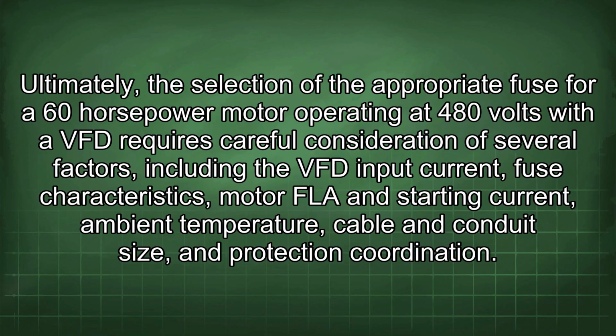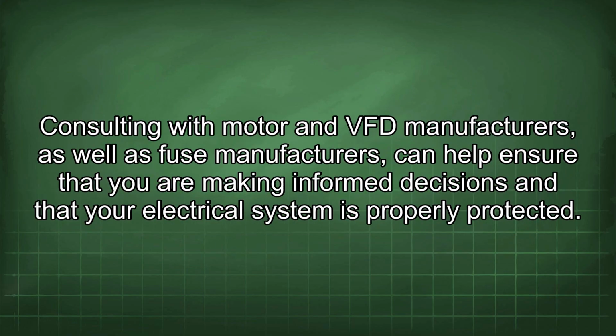Ultimately, the selection of the appropriate fuse for a 60 horsepower motor operating at 480 volts with a VFD requires careful consideration of several factors, including the VFD input current, fuse characteristics, motor FLA and starting current, ambient temperature, cable and conduit size, and protection coordination. Consulting with motor and VFD manufacturers, as well as fuse manufacturers, can help ensure that you are making informed decisions and that your electrical system is properly protected.